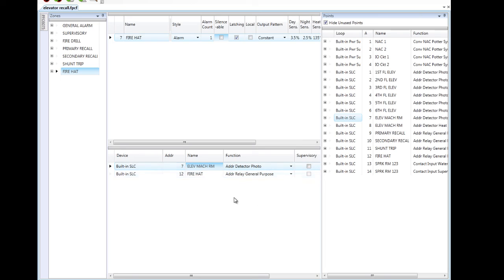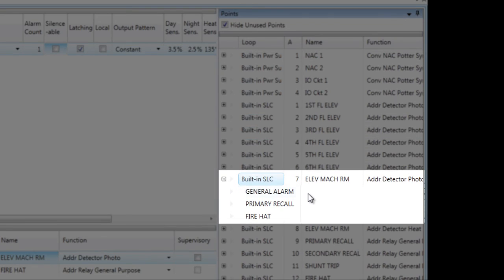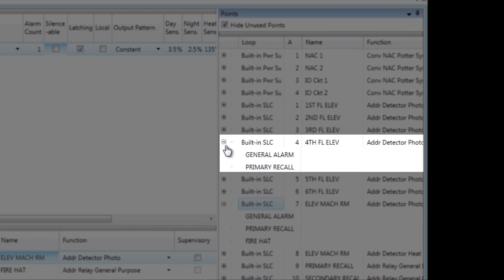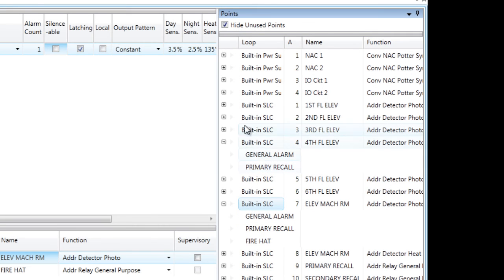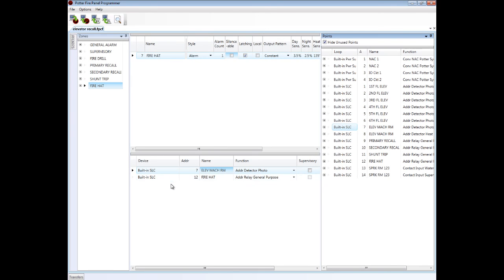For example, this smoke detector in the elevator machine room — if I expand that in the points list, I can see that it's actually in three zones: general alarm, it's triggering the primary recall relay to recall the elevators to the primary floor of egress, and it is also triggering the fire hat in the elevator car. The fourth floor elevator lobby smoke is going to be triggering the general alarm zone for the notification devices in the building, and it is also triggering the primary recall relay. So every point can go in every zone, which makes elevator recall very simple to program in the software.